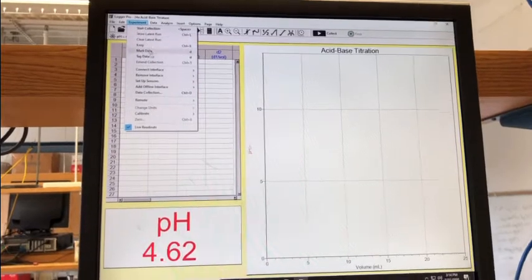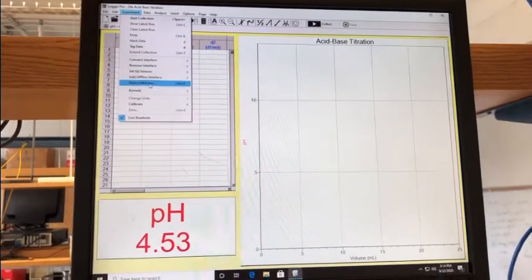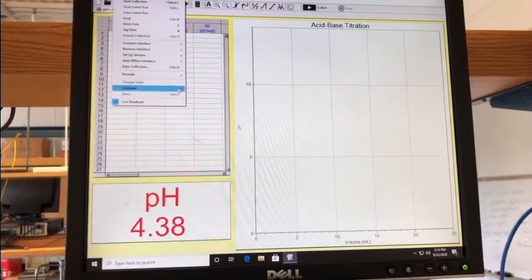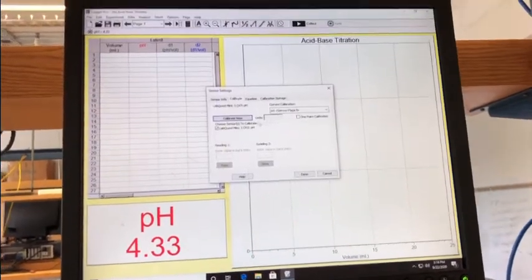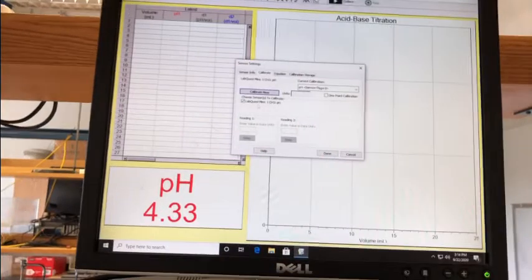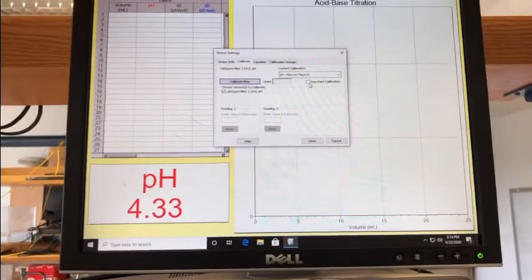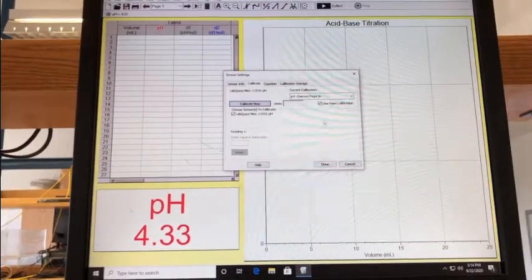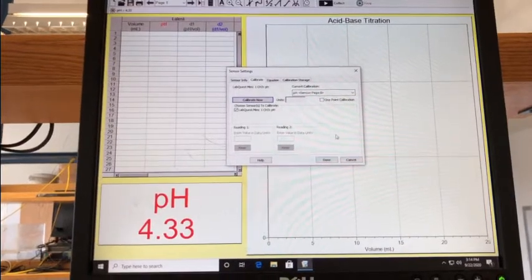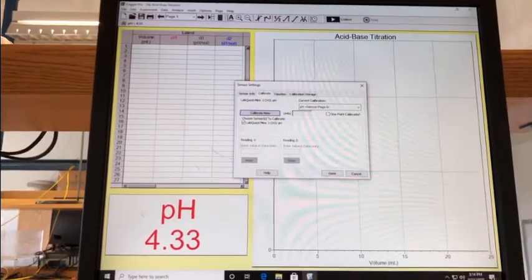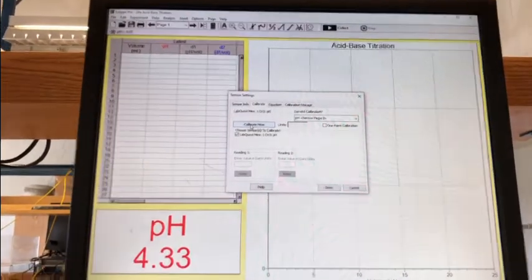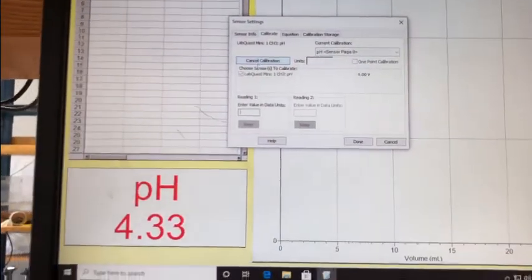the experimental part. Go to the experiment, and then we do the calibration. So here is the calibration. There is a two-point calibration. We are going to do 2-point calibration. If you do 1-point calibration, you have to click it here. Since we are doing 2-point calibration, we select it there. Reading 1, reading 2. So calibrate now. I am going to click calibrate now.